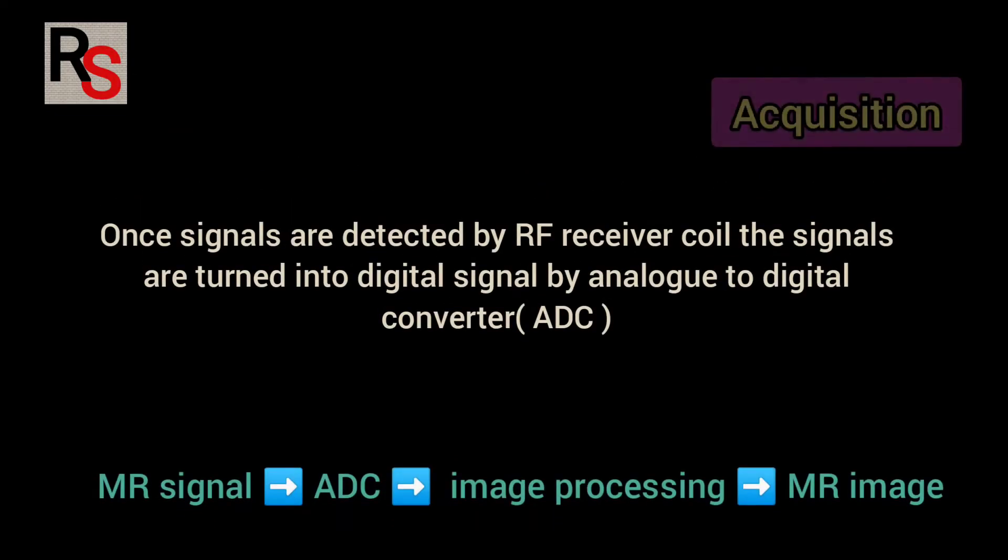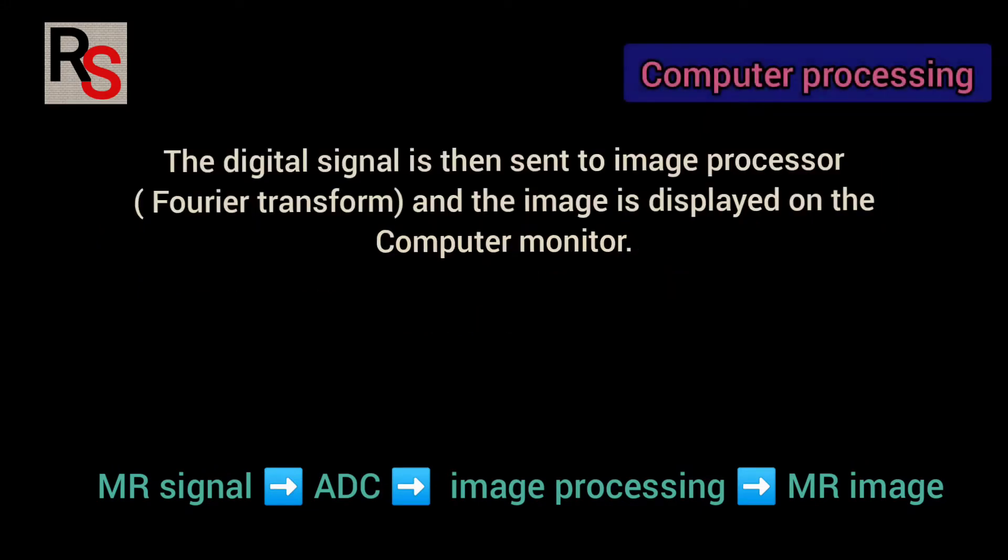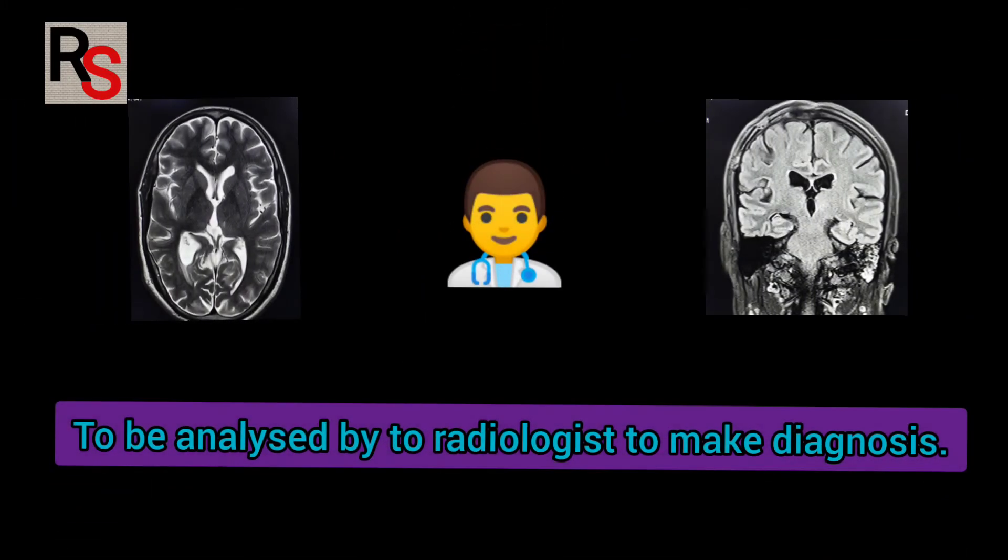Once signals are detected by the RF receiver coil, these signals are turned into digital signals by analog to digital converter. The digital signals are then sent to image processor for Fourier transformation. And the image is displayed on the monitor to be analyzed by the radiologist to make diagnosis.